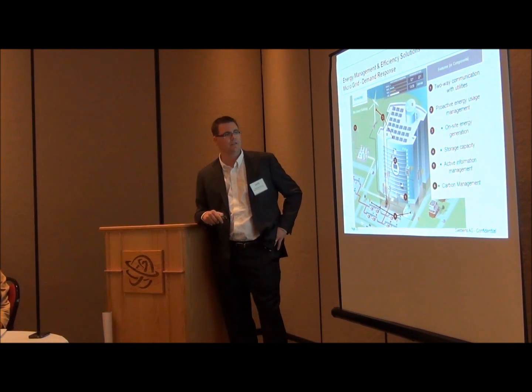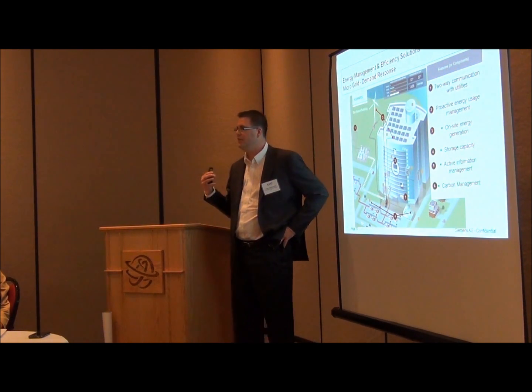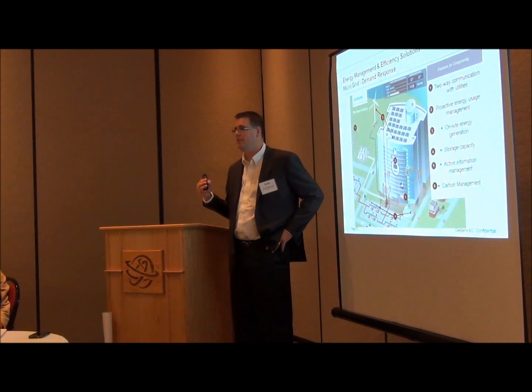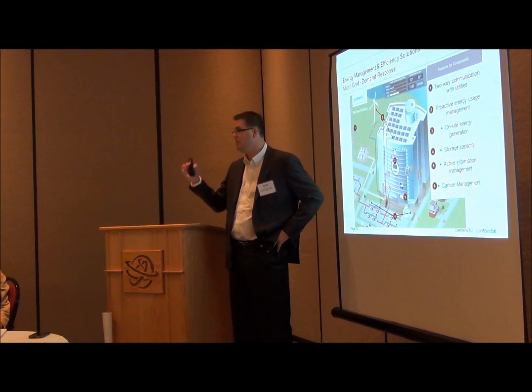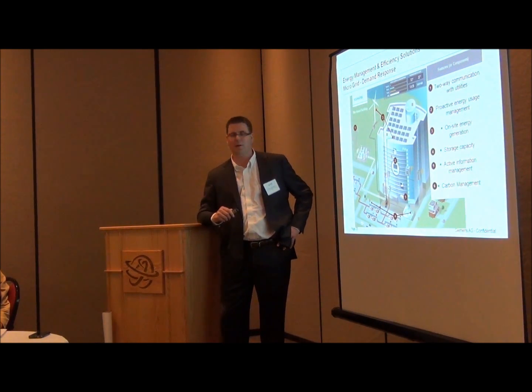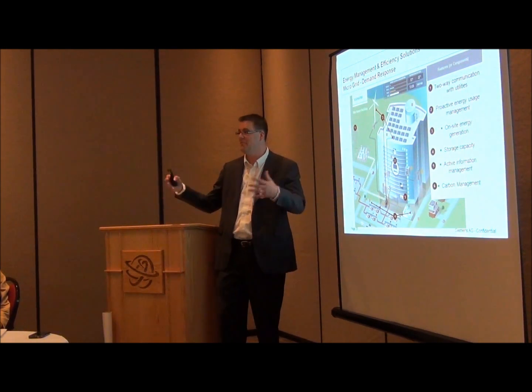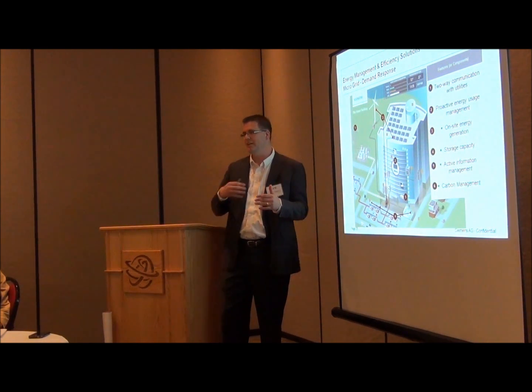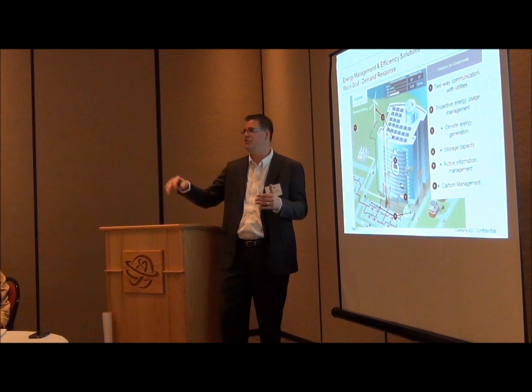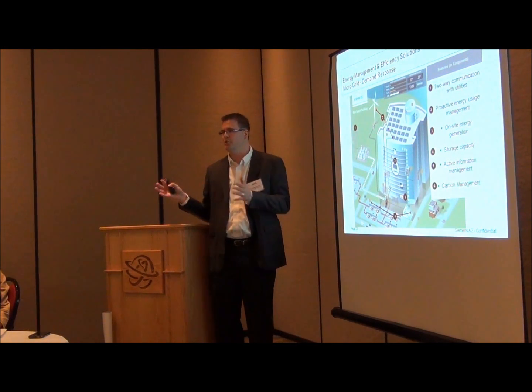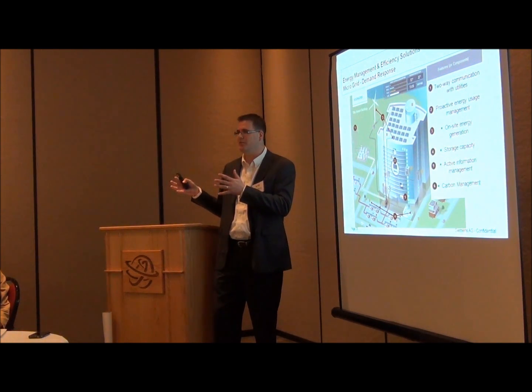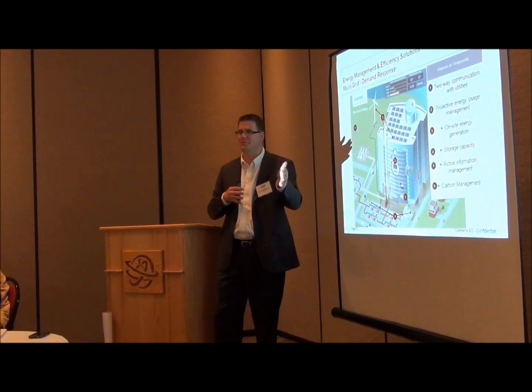You want to interconnect all of these so you can have two-way communication with the utility. If rates are going high today and I'm on a demand ratchet, I'll throttle back my energy consumption pulling from the grid, or use my ice storage during the day instead. At night, when energy's cheap, you make all the ice, and then you run your water through the ice during the day for cooling. So you're shifting the load to make that ice from the middle of the day to the middle of the night.